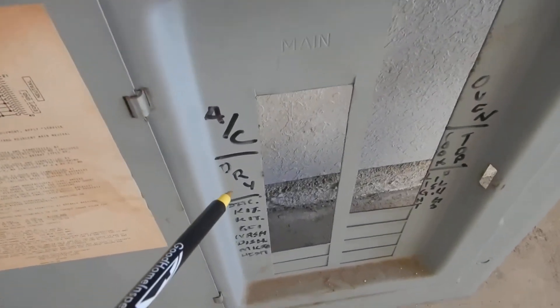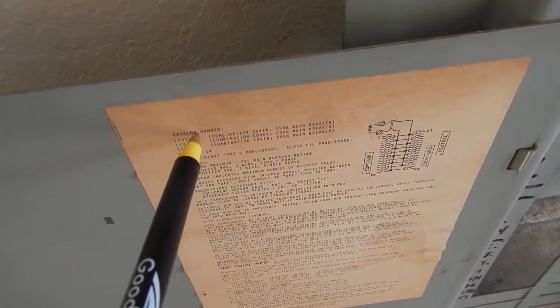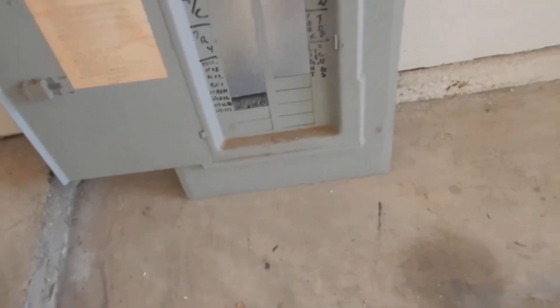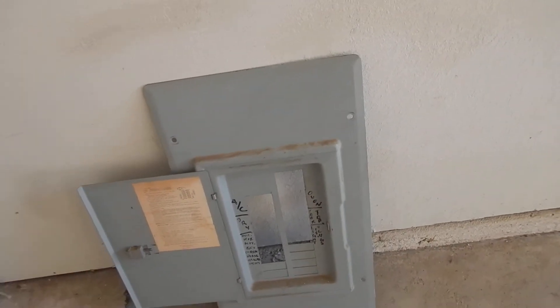These breakers — see how they're labeled? They're supposed to be printed versus catalog numbers. That printing says Crouse-Hinds — that's printed. It's not supposed to be handwritten. I didn't write that; I didn't make that rule up.